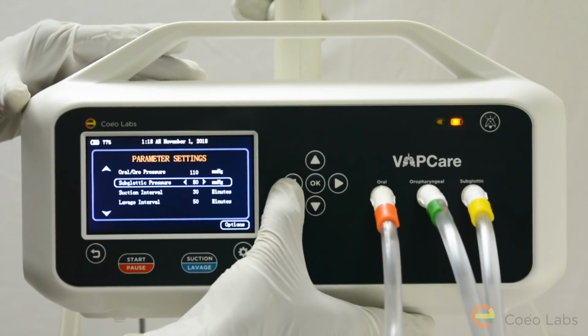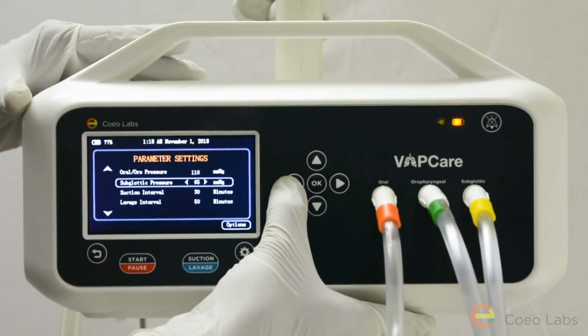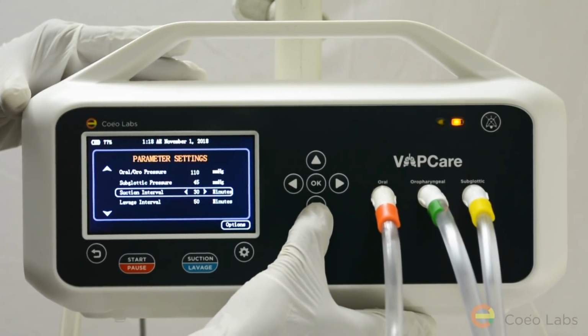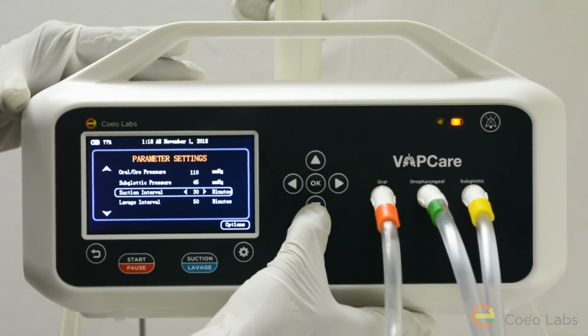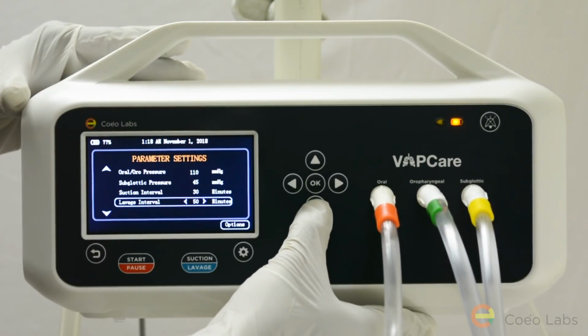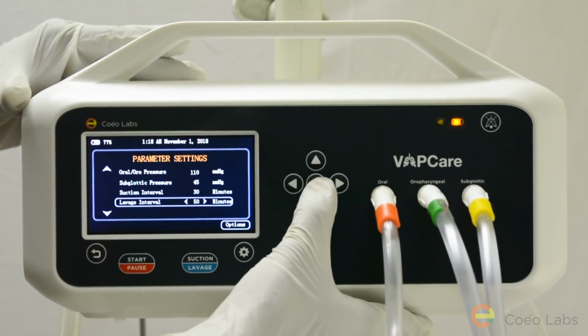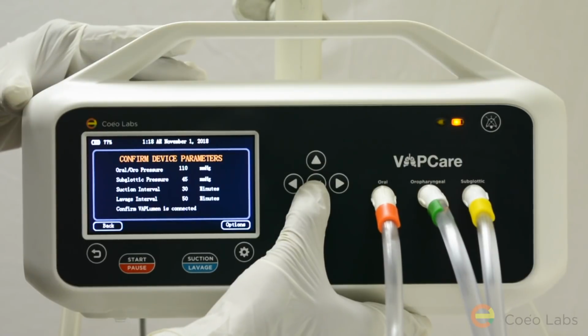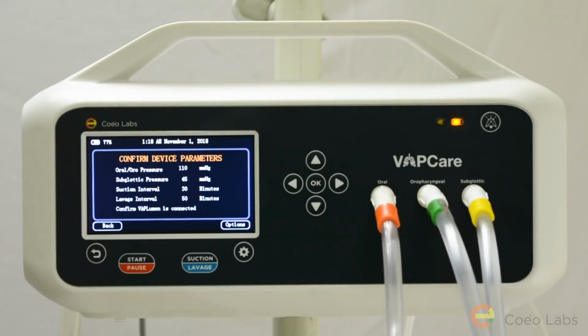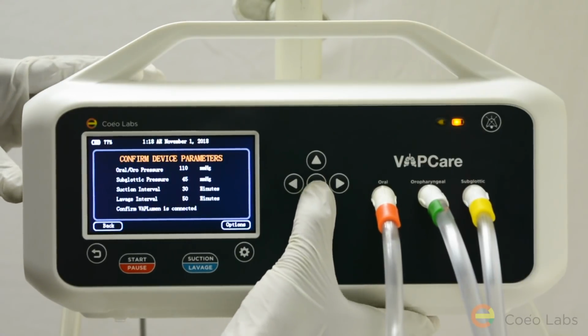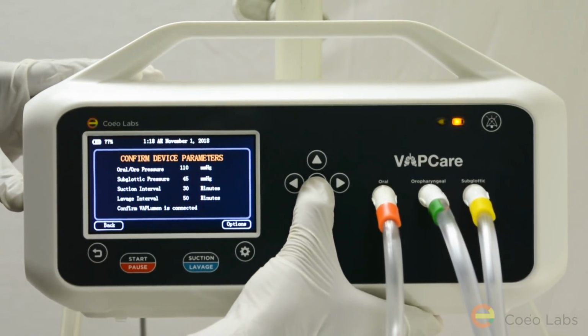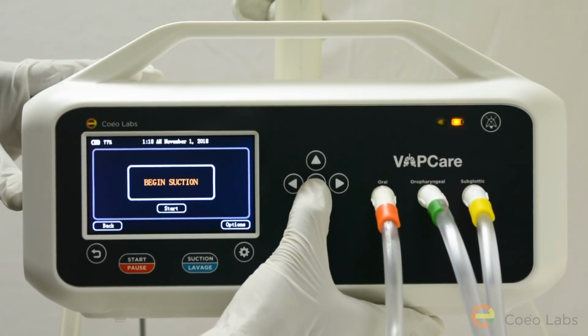The subglottic pressure, I am setting it to 45 millimeters of mercury. And suction interval, for demonstration purposes, I am keeping for 30 minutes and lavage interval as 50 minutes. Once you press OK, the screen prompts for confirmation of the parameter settings. So you can review the parameter settings and then press OK. It goes to the begin suction screen.